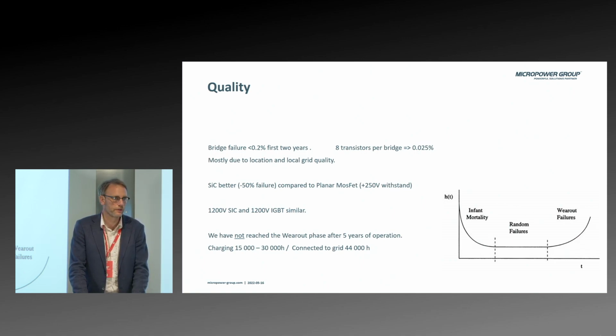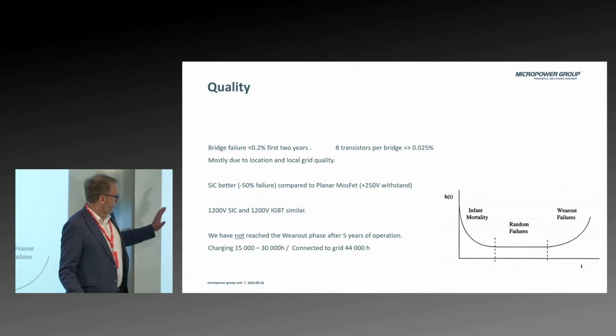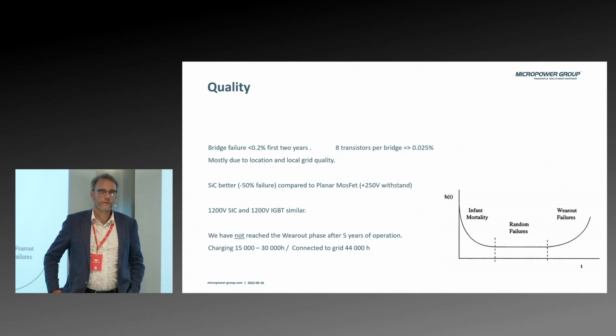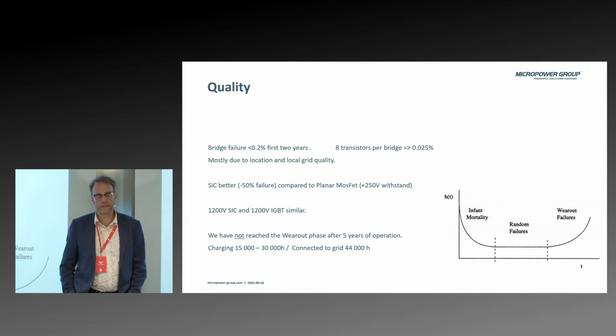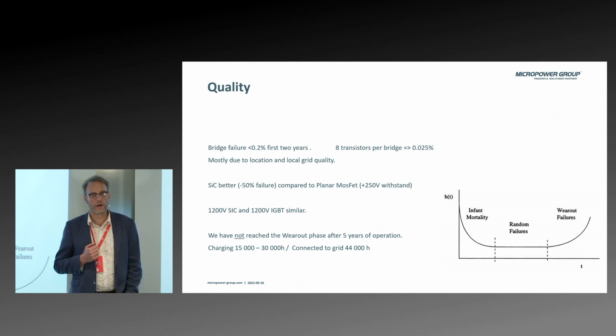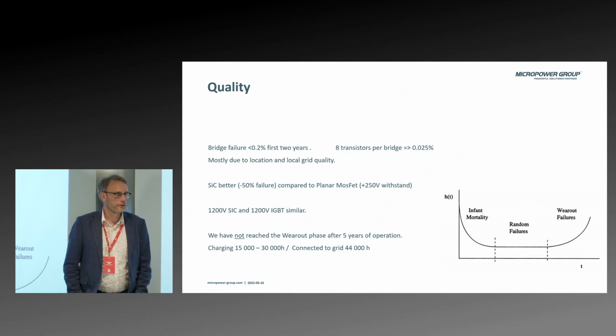By talking to the service workshops, we get about this number, and we're happy with that. So the message is this works very well. If we compare with before, when we had the MOSFETs, we have about half the failure rate now. The reason is probably mainly because we had 950 or 1000 volt MOSFETs, and with silicon carbide we were able to jump up to 1200 volts, so the withstand voltage is better.